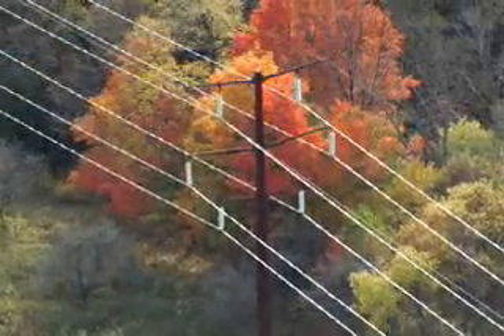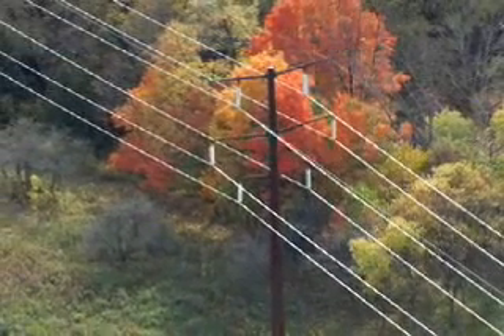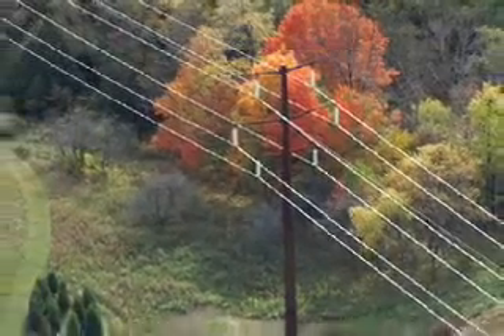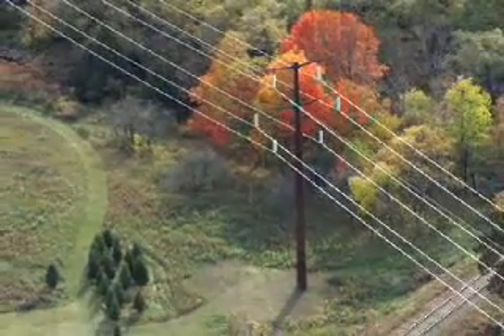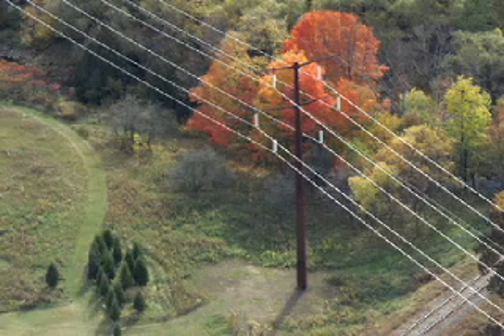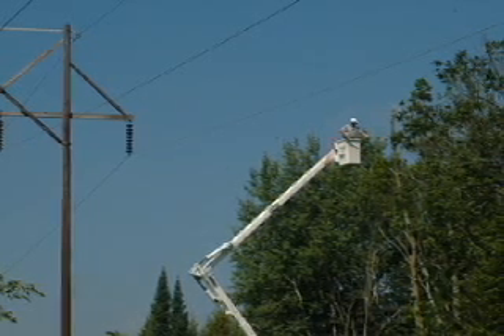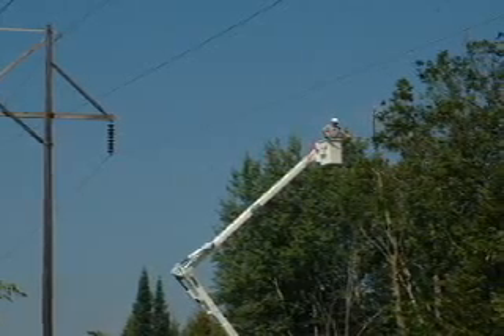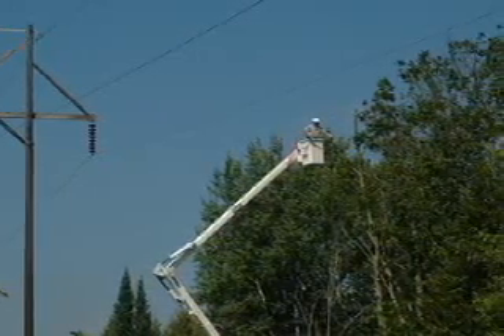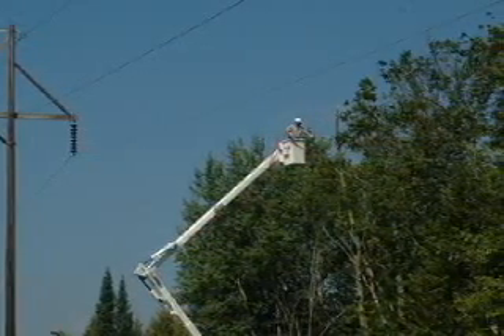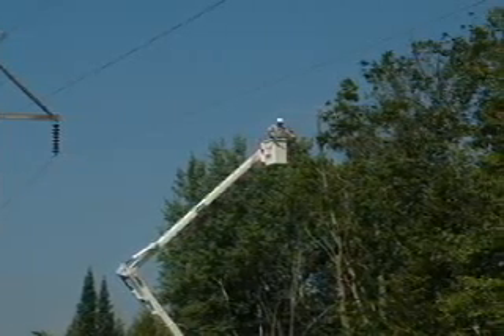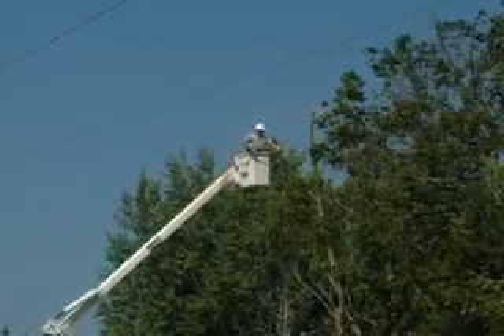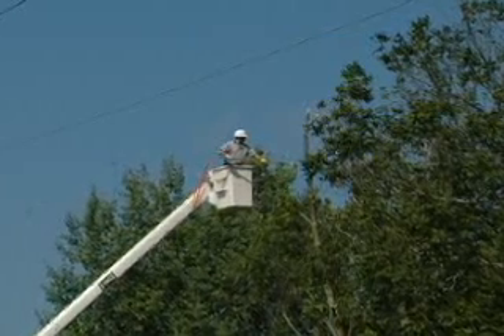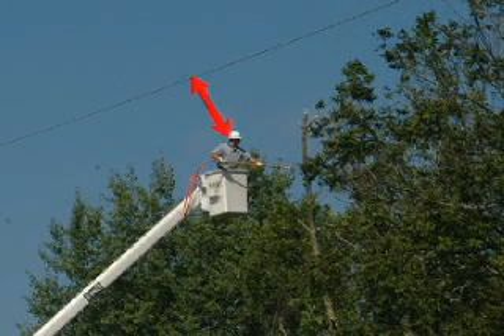Overhead transmission wires are not insulated. If contact is made with an overhead transmission line by your body, your equipment, or your tools, serious injury or death could result. Contacting an overhead transmission line is not the only concern, however. You don't have to come into direct contact with a high-voltage power line to be harmed. If you're working too close to the transmission line, the voltage on the energized line can flash or jump over the air gap to you or your equipment.